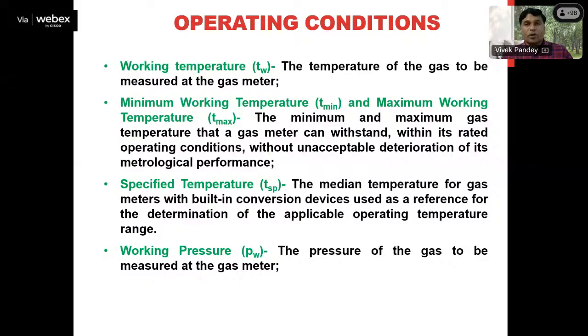Now, when we talk further about the operating conditions, there is a working temperature. That means when the gas meter is being operated for the measurement of gas during a particular transaction, what is currently the temperature of that gas? It is measured by a temperature sensing device, and whatever indication it gives is the working temperature.